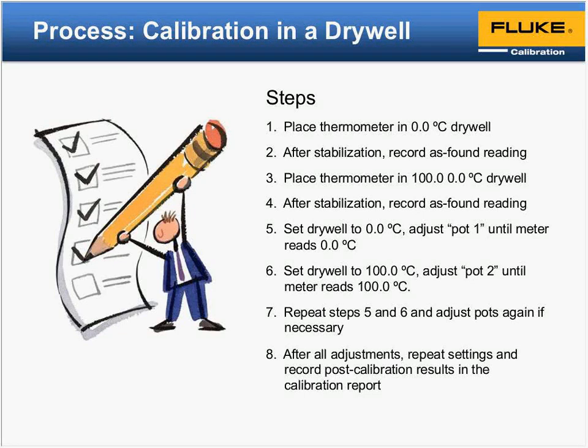All right, so again, back to the setup, similar to the other three. In this one it really changes. We've now added an external reference to improve upon the uncertainty and accuracy that we're going to be referencing. So in the application, we go first to the 0 point, put the unit under test in there, let it stabilize, and take our as found data. Again, it's always critical to get that as found data, in case they are paying for this and don't have in-house testing. You can go back and do reverse traceability to see if they've had compromises in their QA or processes.